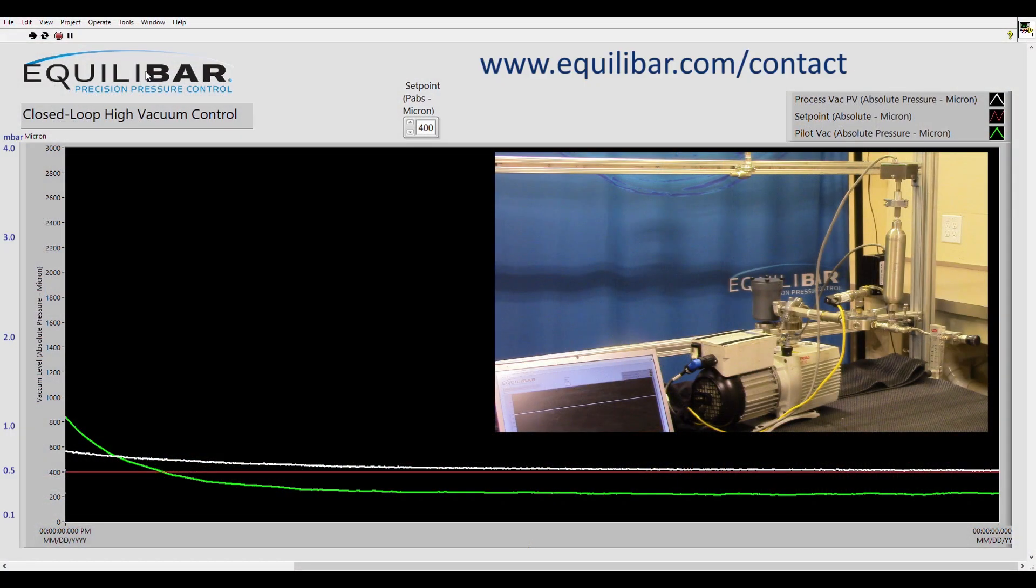Now we've started the pump. We are monitoring and controlling the vacuum process using LabVIEW with a simple PID loop. The controller watches the process pressure sensor and adjusts the pilot pressure command as necessary to achieve the desired set point.